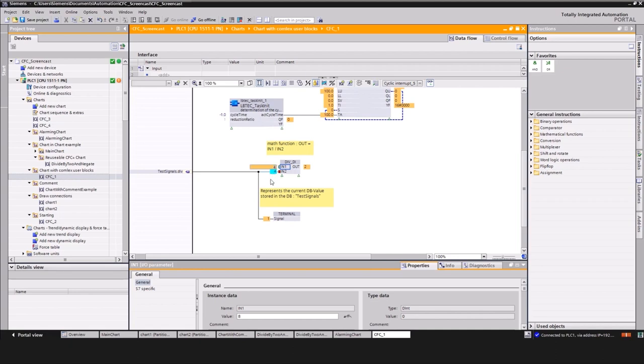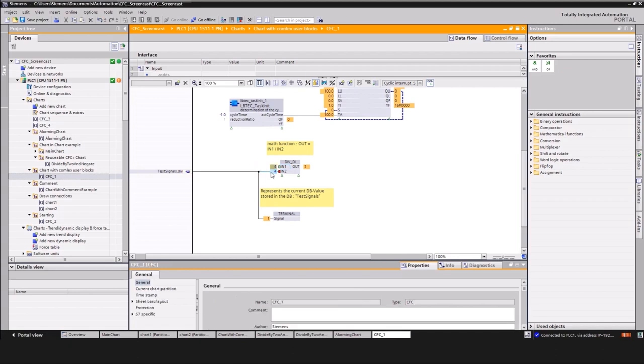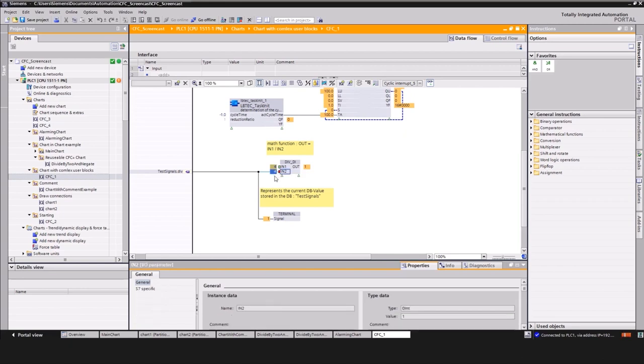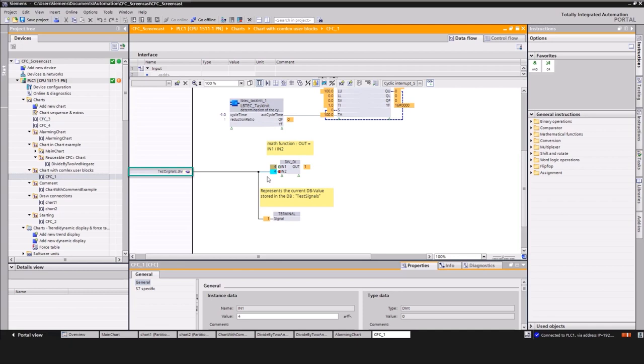I will show you this in the simple example of a block that is used for a double integer division. Just type in a new value and look at the output of the div block. The dividend IN1 is not connected and as you can see only a simple forcing is activated. The divisor IN2 is connected to a fixed DB signal with the value of 1, as you can see on the block terminal. The connection to this global DB signal that is located in the normal user program shows that CFC gives the user the possibility to interact with other program languages, especially Graph S7.